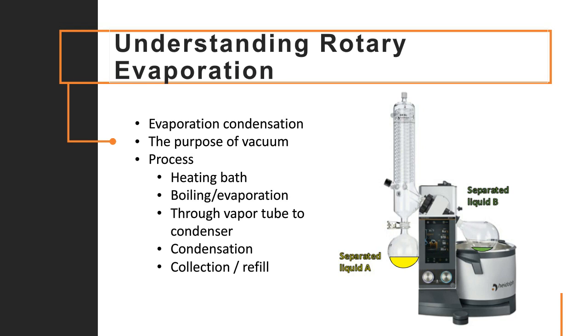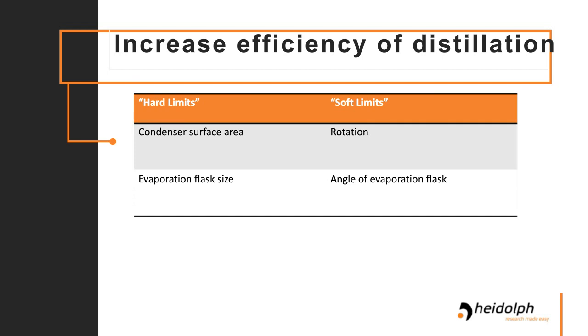So now we're going to talk about increasing the efficiency of your distillation, basically making sure you can distill as fast as possible without even adjusting the heating or the pressure of your system. There are two different kinds of limits I like to consider. Hard limits, which I basically think of as things you consider while you're buying your rotary evaporator, and then soft limits, what can be adjusted after that point. Some of those hard limits include the condenser surface area and the evaporating flask size, while some of those soft limits are your rotation speed and the angle of your evaporation flask.